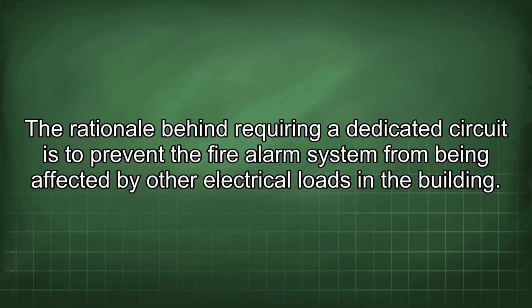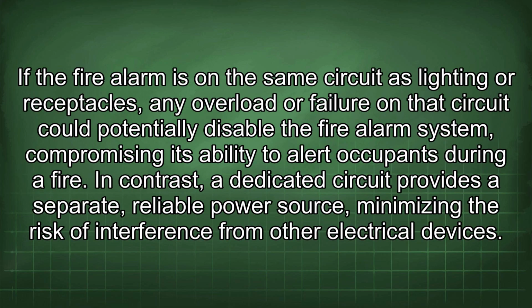The rationale behind requiring a dedicated circuit is to prevent the fire alarm system from being affected by other electrical loads in the building. If the fire alarm is on the same circuit as lighting or receptacles, any overload or failure on that circuit could potentially disable the fire alarm system, compromising its ability to alert occupants during a fire. In contrast, a dedicated circuit provides a separate, reliable power source, minimizing the risk of interference from other electrical devices.